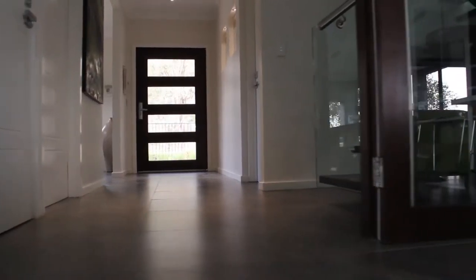And obviously zoning at the main living space as well. We've zoned a lot of areas of the house just to minimise the volume of air that you want to condition — so if you're running the air conditioning system it's not working so hard to heat or cool the entire house. What we found is that we were able to halve the size of the air conditioning unit compared to what the industry standard says.